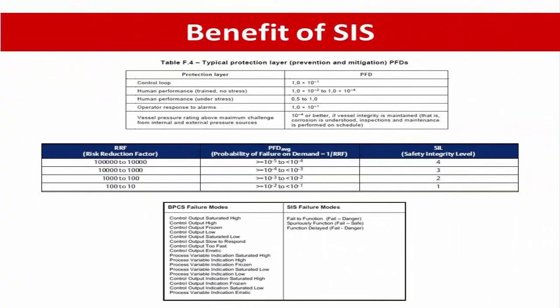What is the benefit of the SIS? One factor we can use to compare benefits is the Average Probability of Failure on Demand, or PFD average. The BPCS, which is a control loop to prevent an impact from occurring when the initiating cause occurs, can achieve a minimum PFD average of around only 0.1, as shown in the table. But the SIS consists of several Safety Instrumented Functions, and each SIF has a specific Safety Integrity Level, or SIL, that must achieve a required PFD average depending on the necessary risk reduction, ranging from SIL 1 to SIL 4.